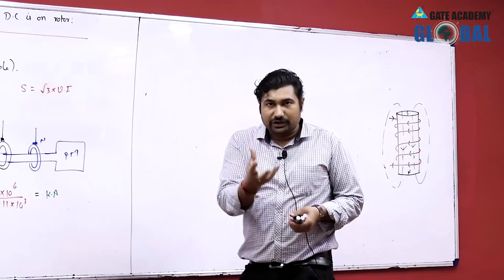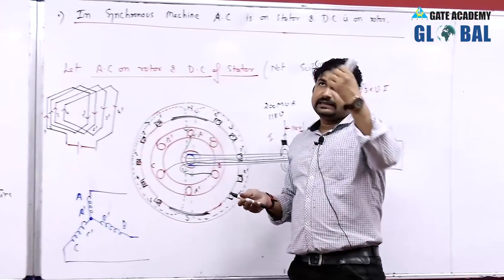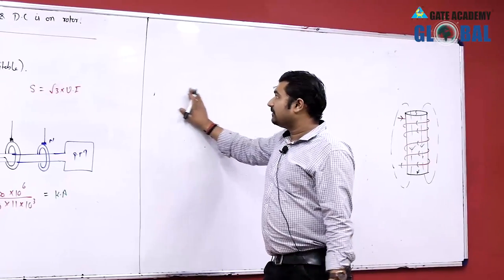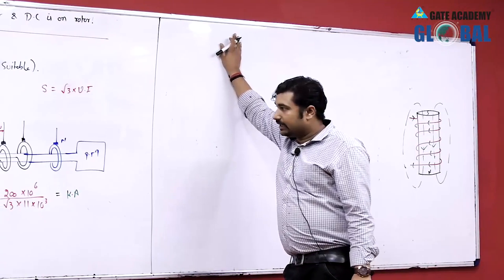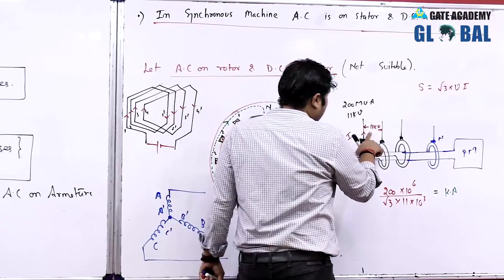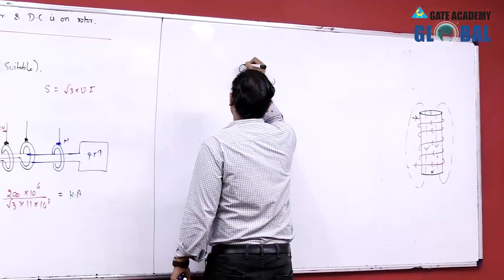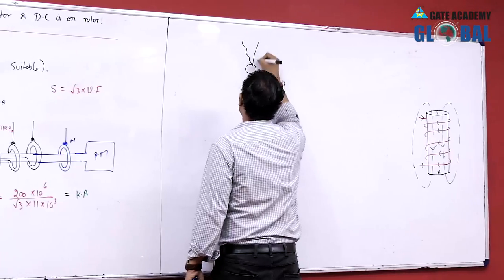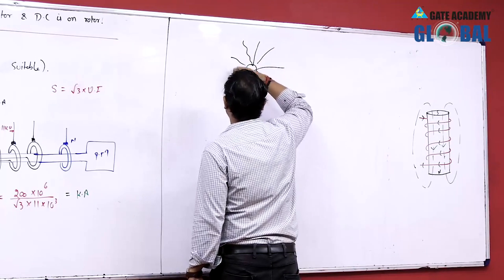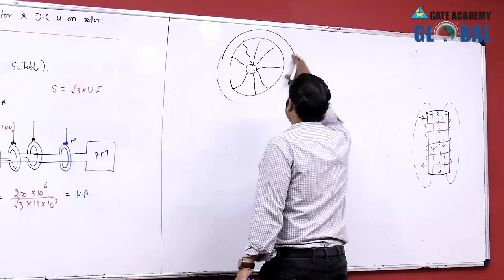In order to reduce the size of a machine, we have to reduce the overall insulation. Voltage rating depends upon the insulation level provided. The wire used in the rotor would need an insulation level of nearly 11 kV/√3, which is very high. This requires a very large diameter size of slip rings.